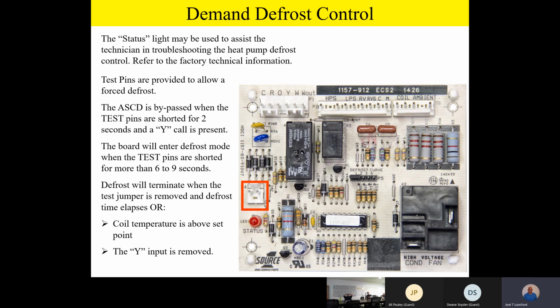And finally, once you go into a defrost, let's say, for instance, you force a defrost, if you have a coil sensor that's out of calibration, it may go into defrost and stay in there until it hits the 14-minute time backup. So either way, if you're hitting the 14-minute time backup, you've got a bad coil sensor. If it jumps out of defrost right away when you jumper it, you might have a bad coil sensor as well. And remember, team, these coil sensors will fail one of two ways.